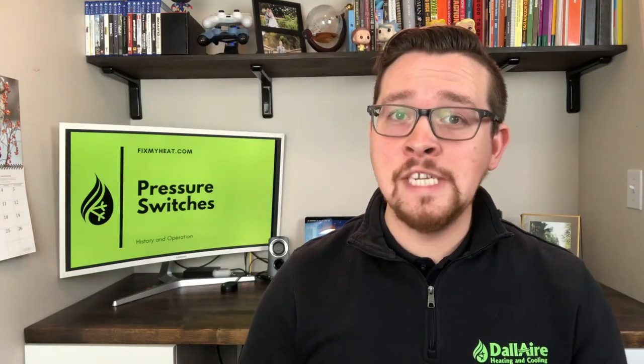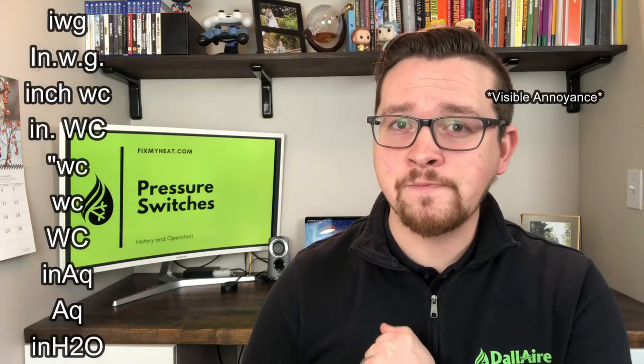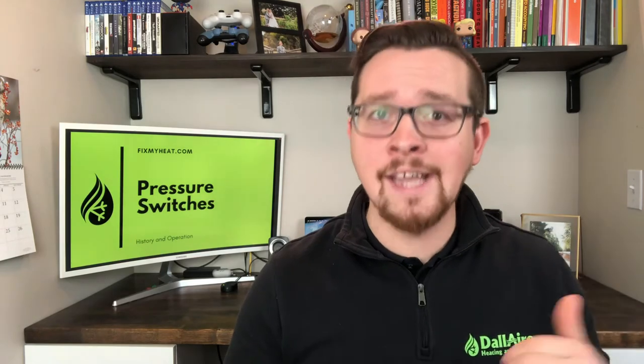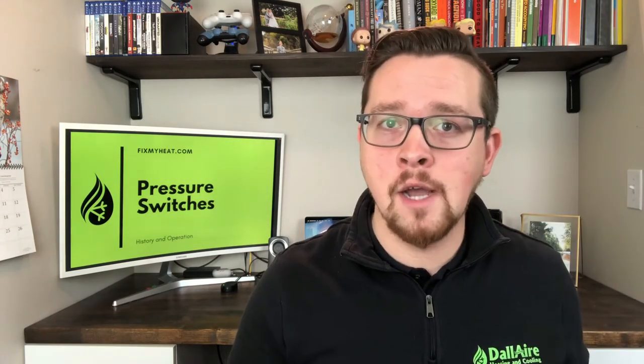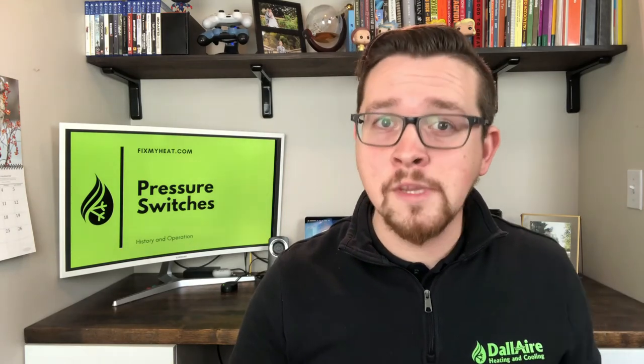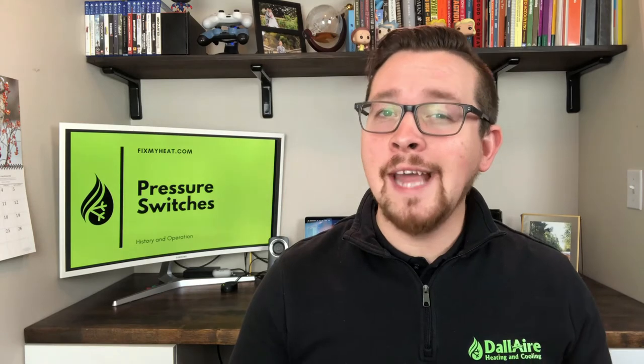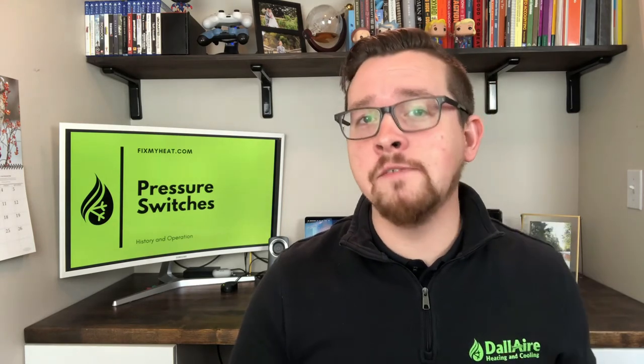Inches of water column or inches of water gauge are generally labeled in one of 10,000 ways. I generally will use a quotation mark and the letters WC, and most technicians know that I'm talking about inches of water column, and it's relatively easy to type into my service notes. Regardless of how or if the switch is labeled, it will be rated for a specific positive or negative pressure rating in inches of water column. If the pressure switch port is located before the exhaust assembly, it's normally a negative pressure switch. And if it's located after the exhaust assembly, it's normally a positive pressure switch.